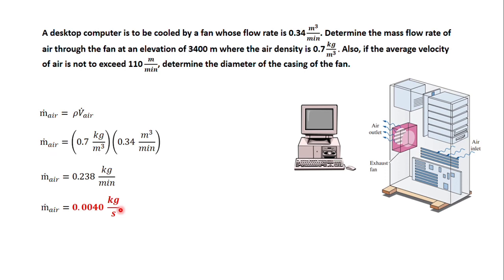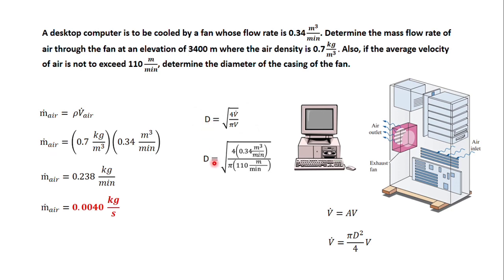If the mean velocity is 110 meter per minute, the diameter of the casing is found using d equals the square root of 4 times the volumetric flow rate divided by pi multiplied by velocity. This formula is derived from the volumetric flow rate equals area times velocity, where the area for a circular cross-section is pi d squared over 4. Plugging in the values: diameter equals the square root of 4 times 0.34 cubic meter per minute divided by pi times 110 meter per minute, giving a diameter of 0.063 meter.